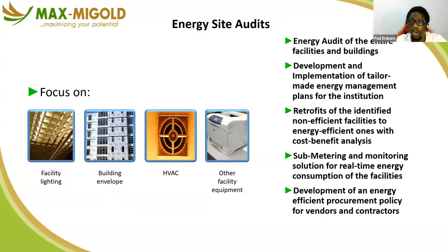Some HVAC systems are so old that in trying to overcome their maintenance problems over the years, they draw more and more energy. Equipment rated at 13 kilowatts, for example, may be tapping 17 kilowatts continuously to overcome the resistance caused by poor maintenance and age. That difference of 4 kilowatts alone, multiplied by runtime and frequency of operation in a year, can in some cases equal the cost of acquiring brand new systems.